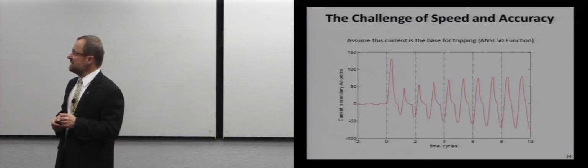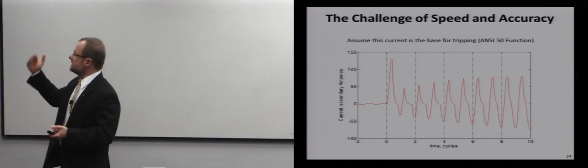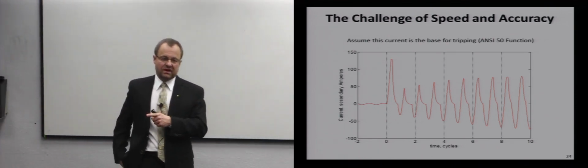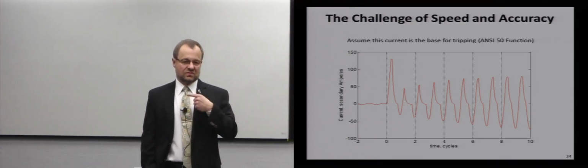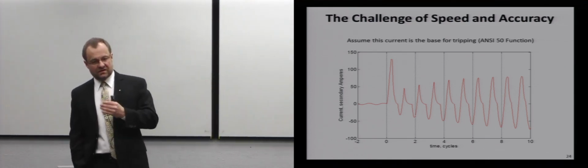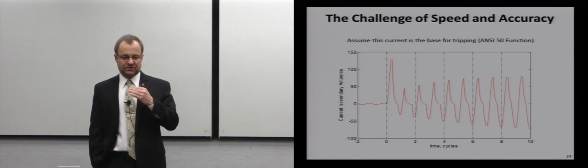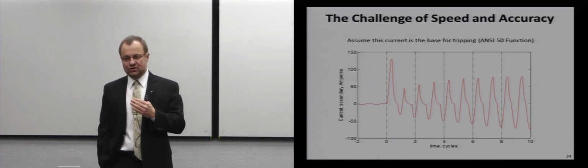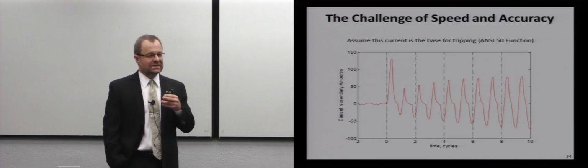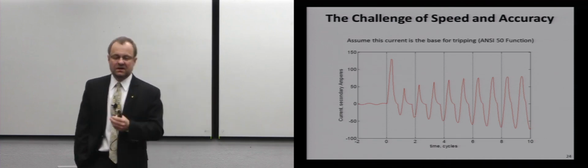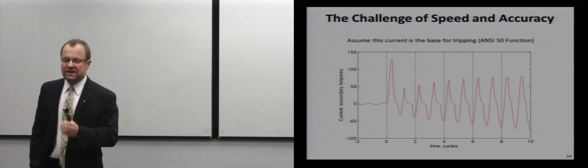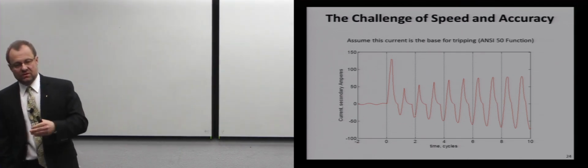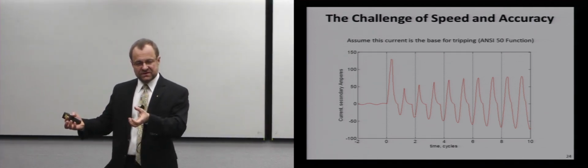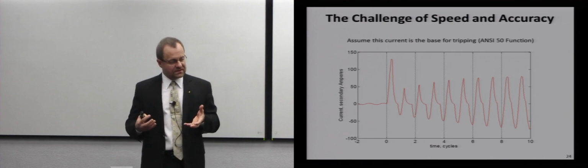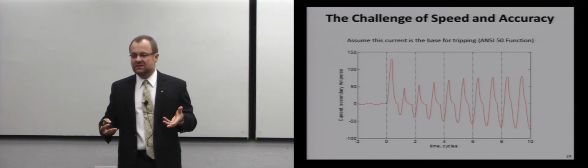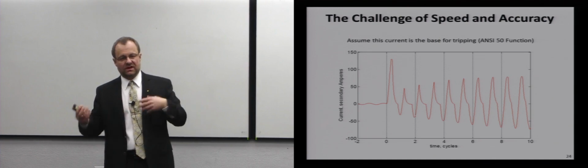So I picked the simplest function possible, the 50 function, which is, you should know by now, a straight instantaneous overcurrent, right? If the current is above a certain threshold that came from a user as a setting, you trip. You should do it because it's not 51, which is time delayed, intentionally time delayed. It's 50, meaning instantaneous. You want to do it as soon as possible. So all your scans, passing data from one piece of silicon to another, it's all optimized, so we are not wasting time waiting for data to move from one memory location to another.